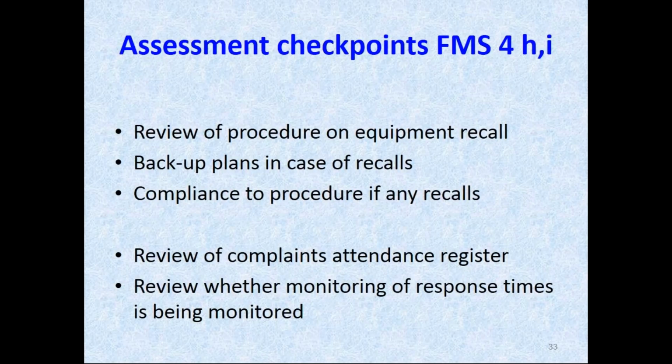If any recall has occurred, we need to check what procedure has been followed. Regarding the response times monitoring, we need to look at the complaints attendance register, whether the different times have been noted, the time of complaint registering, the time of attending the call, and the time of ultimate resolution, and to check whether these response times are being monitored for further action.